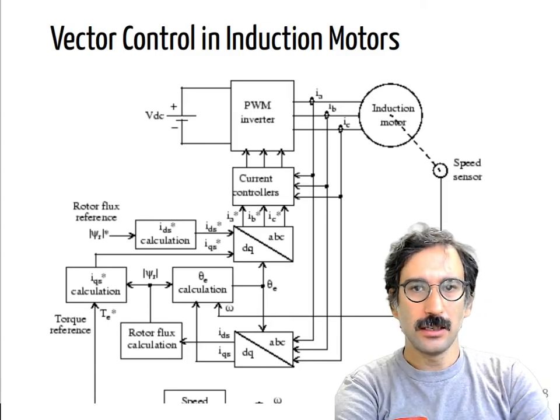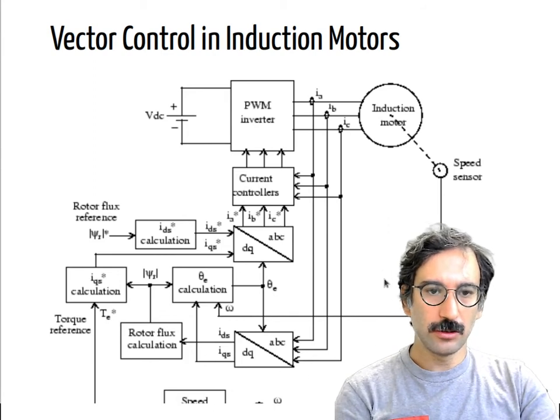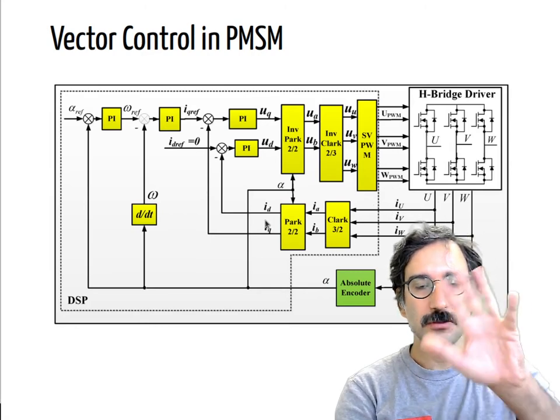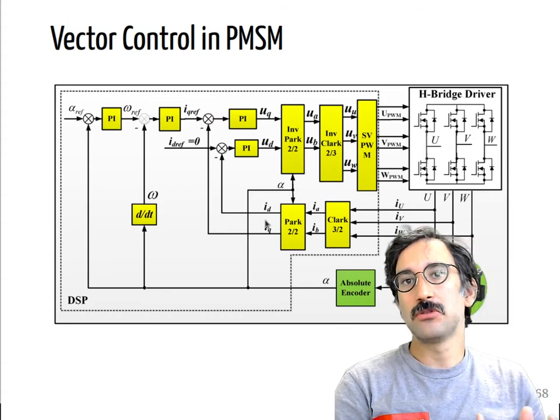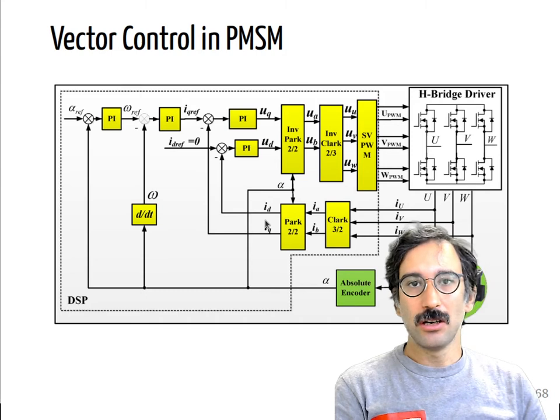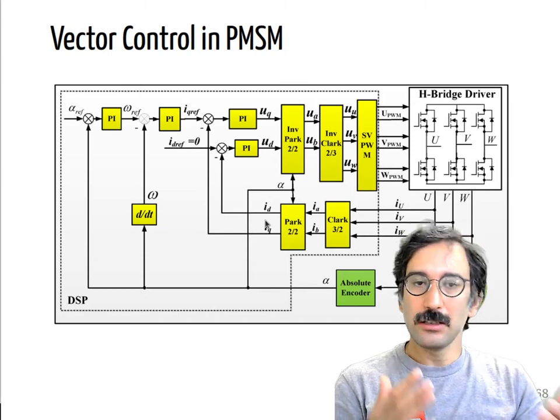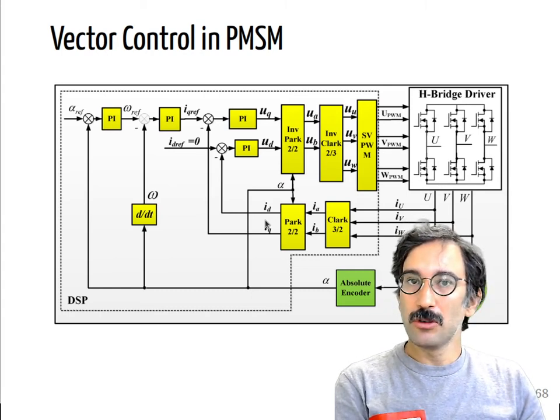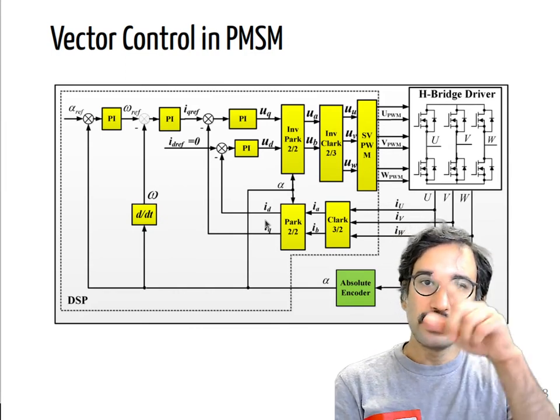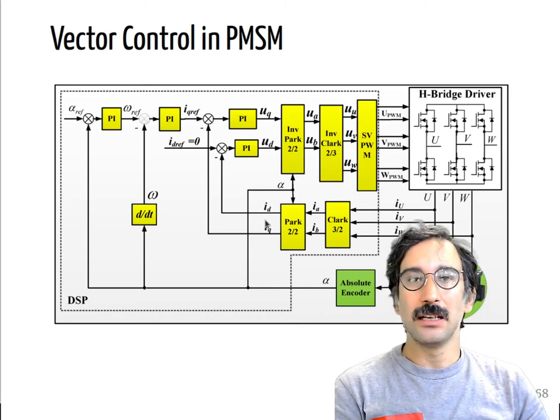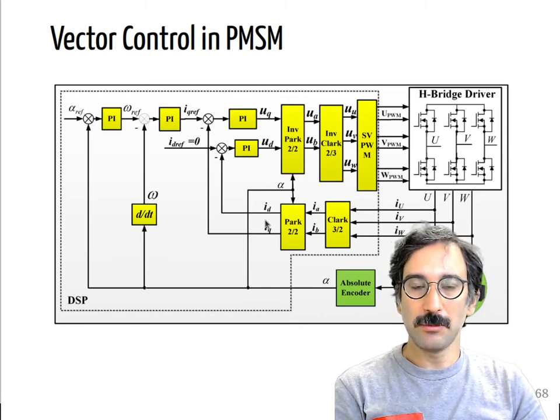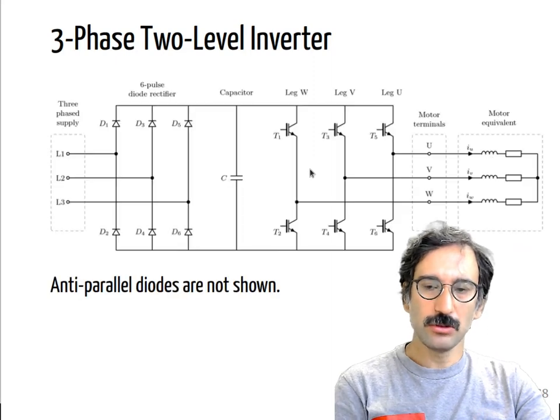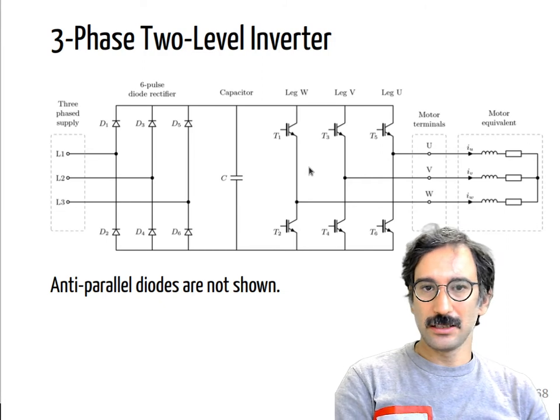In the last lecture we talked about field oriented control of electrical machines. The normal idea is to use the Clark and Park transformation to get an idea of the rotor position and what should be the exact position of the applied voltage or currents. You can apply the inverse Clark and inverse Park transformations to get real sinusoidal voltages and then apply sinusoidal PWM, but there are more efficient and easy methods to do that.